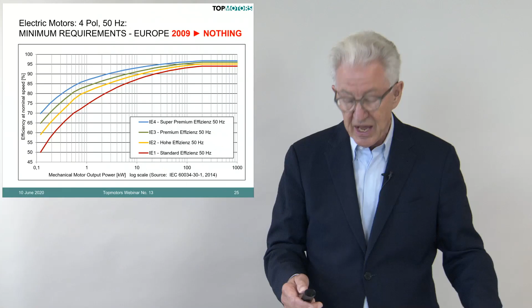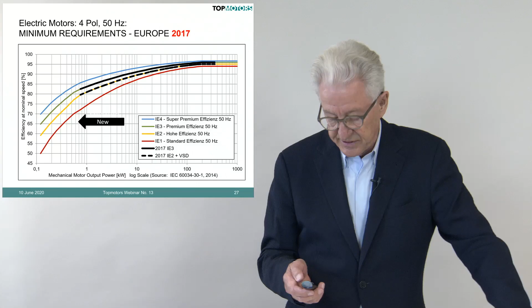2015: Europe decided for the first time to introduce a minimum requirement, and you see now two black lines. The upper black line, at the IE3 level, was required between 7.5 kilowatt up to 375 kilowatt, and there's a dotted black line below that, introduced at the same time, as an alternative to the IE3: you could use an IE2 motor, that means a little bit less efficient, if you use it together with a variable speed drive. Now we go to 2017. That was the second tier of the European requirement. It was expanded to go from 0.75 up to 7.5 kilowatt. The black arrow shows the expansion, but it was the same game, with the black line on IE3 and the black dotted line on the IE2 plus the variable speed drive.